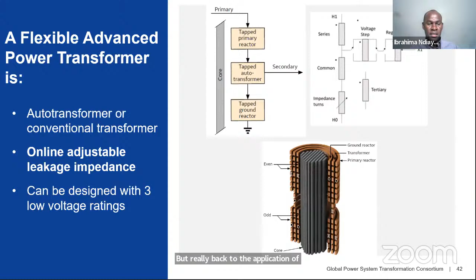Obviously, a tap changer, as we know today for on-load tap changers for voltage, can be controlled remotely. If you do the same for leakage impedance, then we can control the leakage impedance of a transformer remotely. This technology can also be built with different voltage ratios—at the end of the presentation I can explain why—just to make it a more comprehensive technology. But back to the application of having a leakage impedance, if we go to the next slide, you can see there's a different way today to do power flow control.